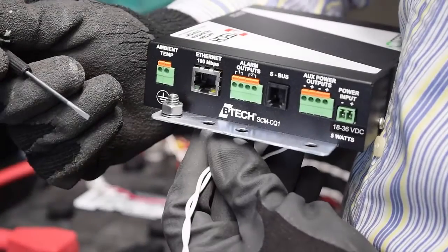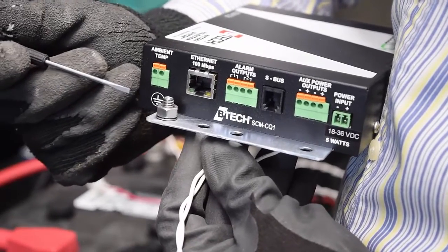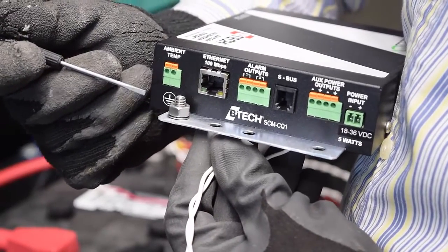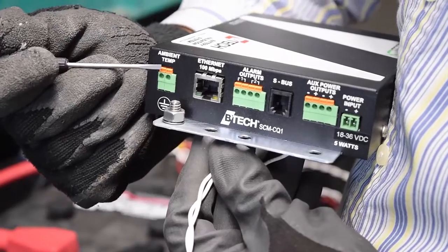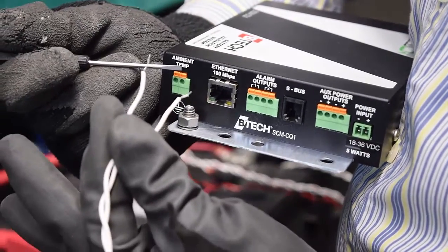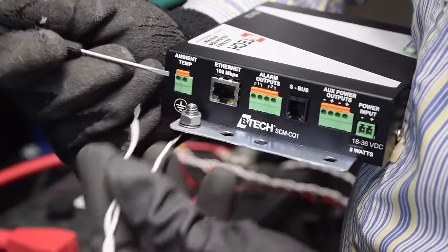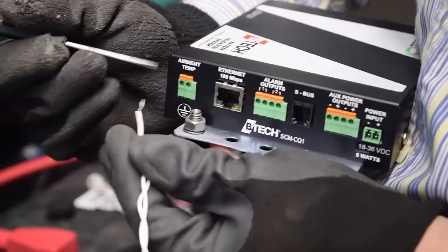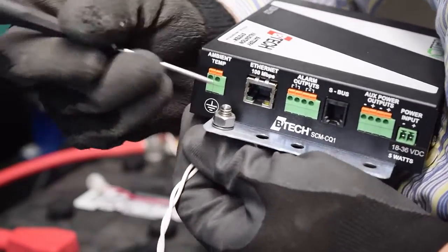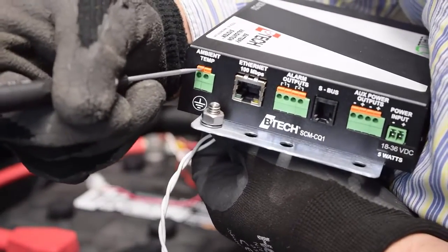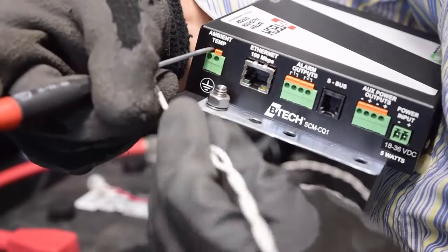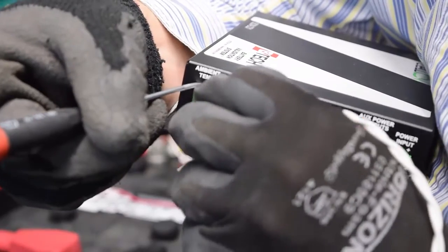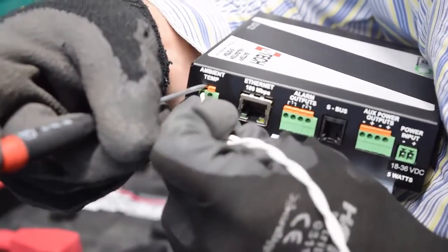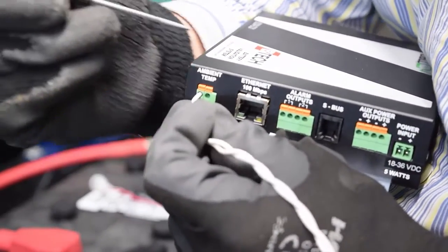So before we mount the CellQ1 controller, we want to connect the ambient temperature sensor to this connection here. It's a twisted white pair of cable, and the way to install it, you want to use your screwdriver and press in the orange part. Then you can put in the wire and pull out, and that's it.